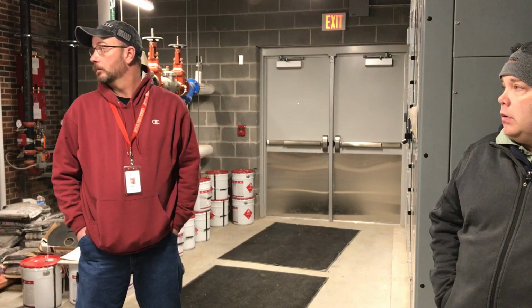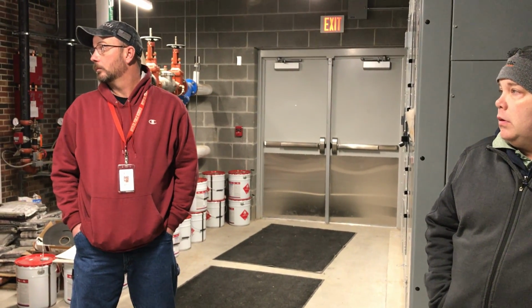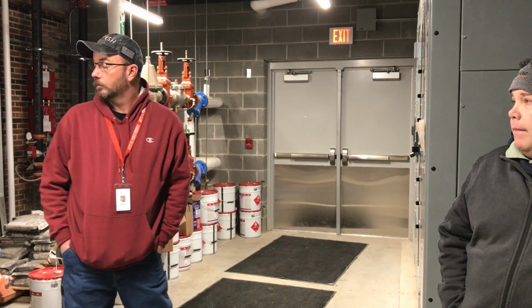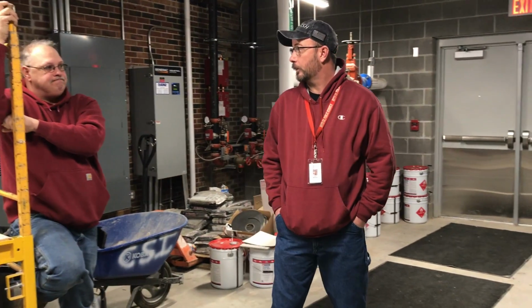You know, this building's got more of a load on it than you realize. With all the emergency lighting plus the cooler, freezer, condensers and stuff, I'd say you're getting close to 60, 70 amps on load run anyhow, maybe more than that. The only thing that helps is the LED lights, that helps. Yeah, it helps, but you've got 10 circuits in the gym loaded with LED, and you're gonna have the startup of the refrigeration that's gonna draw a load for a second.